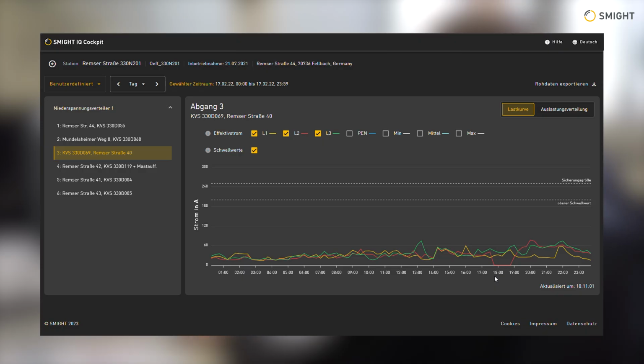This was an indication that a fuse had tripped in this substation. L1 and L3 were still working, but the current flow went to 0 on L2. We were then able to send the technician directly to the substation to check the fuse there, and the fault was rectified very quickly. He didn't have to go to the house connection or check the cable distribution cabinets first. Instead, he was directed straight to the substation where the problem was.